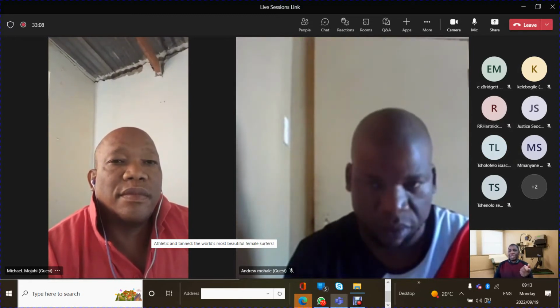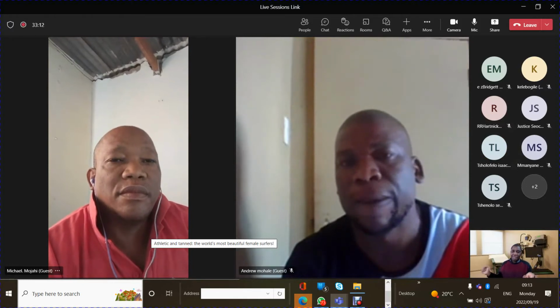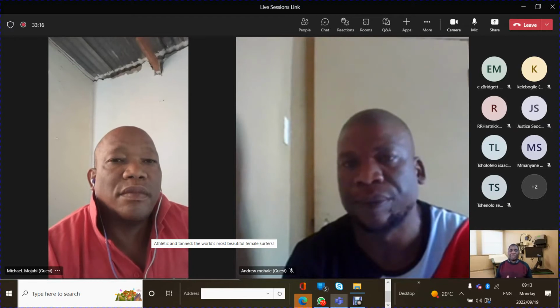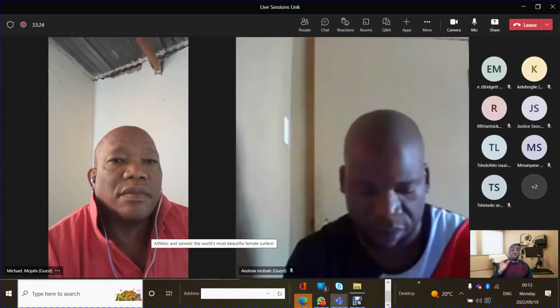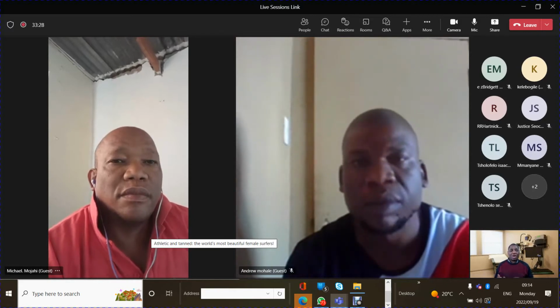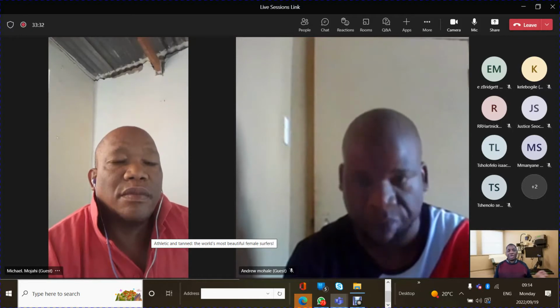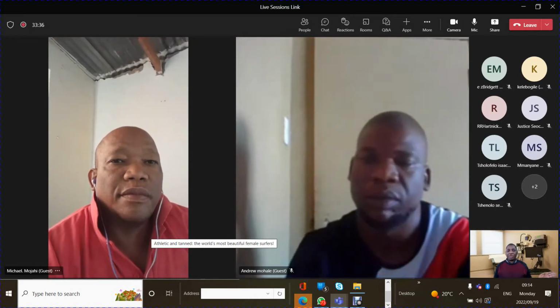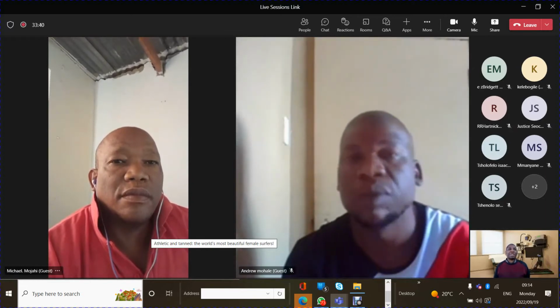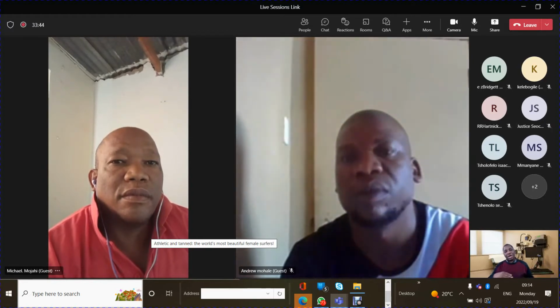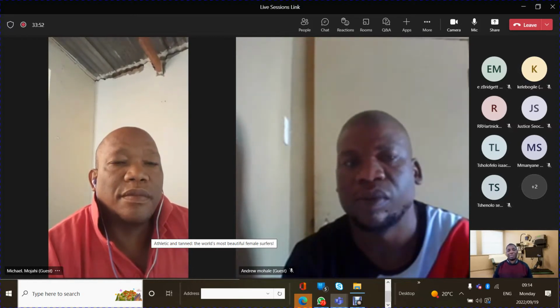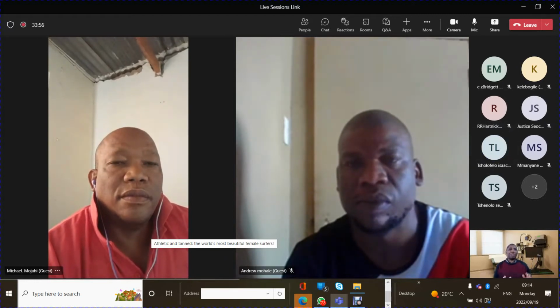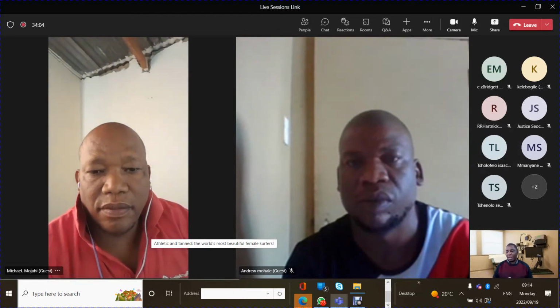So when you set your energy on the defibrillator and then discharge and test with your defib analyzer, it should correspond exactly, or at the least not be more than 10% outside of what you've set. If you set 100 joules, for instance, as your energy on the machine, and then you test, you discharge on the analyzer, you should get between 90 and 110. Your tolerance should be 10%, not more than 10%, plus or minus. So if you set 100, it should be between 90 and 110. So outside that range, then there's a problem.